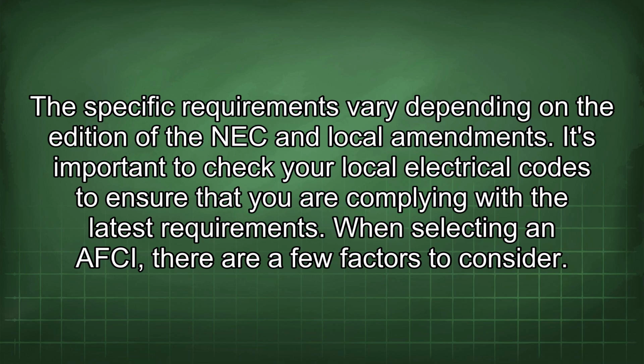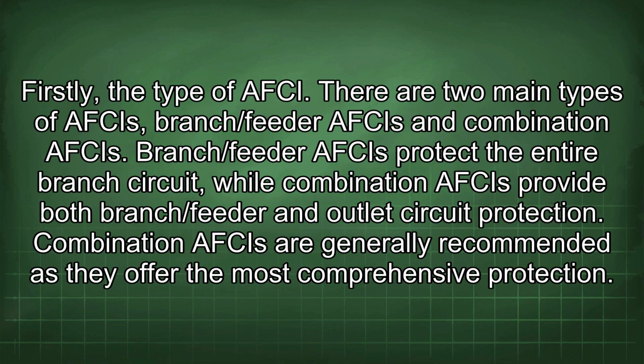When selecting an AFCI, there are a few factors to consider. Firstly, the type of AFCI. There are two main types of AFCIs: branch/feeder AFCIs and combination AFCIs. Branch/feeder AFCIs protect the entire branch circuit, while combination AFCIs provide both branch/feeder and outlet circuit protection. Combination AFCIs are generally recommended as they offer the most comprehensive protection.